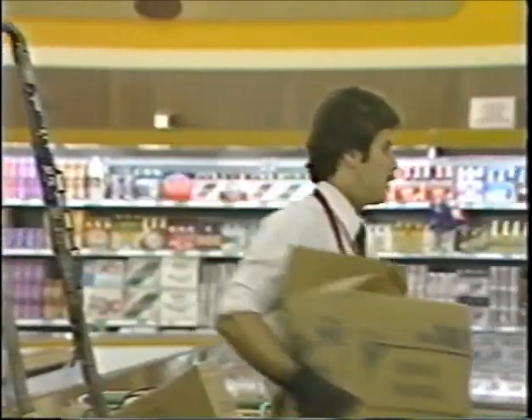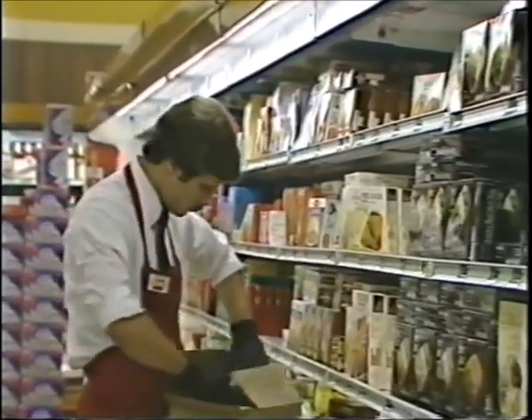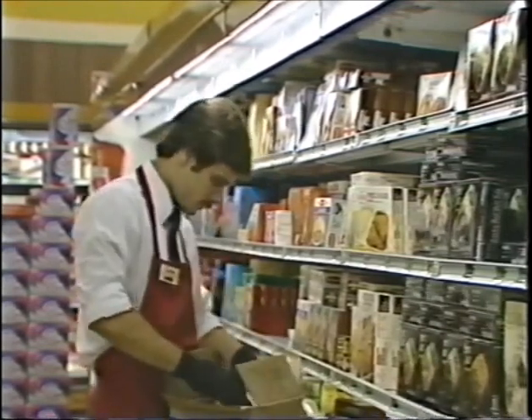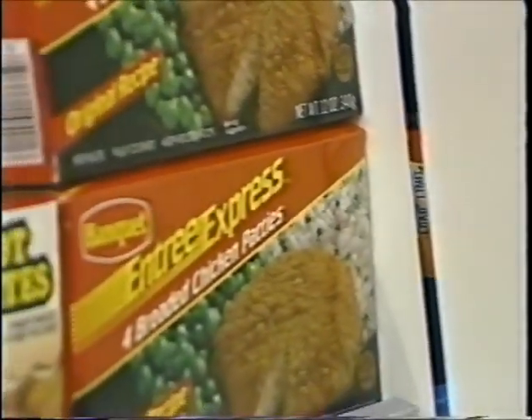After the cases are completely cleaned, they need to be restocked. Proper loading or stocking of the display cases is an essential part of energy conservation in your store. There are three basic rules: one, move merchandise rapidly from the cooler box into the display case; two, rotate the merchandise; three, do not place merchandise outside of the refrigerated display area of the case — observe the load limit lines. These rules are important because display cases are designed to remove the heat from the air surrounding the product, not to remove heat from the product itself.